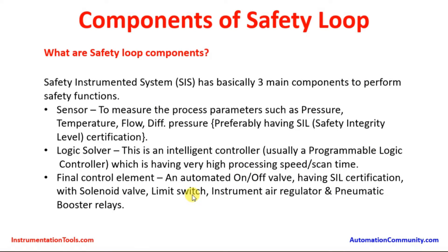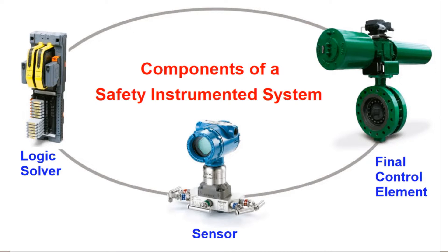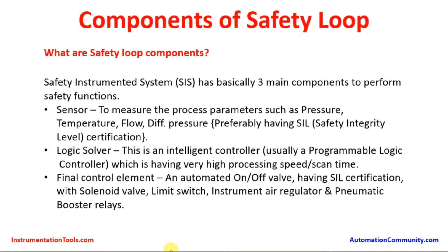The third component is the Final Control Element. This is an automated on-off valve having SIL certification, with a solenoid valve, limit switch, instrument air filter regulator, and pneumatic booster relays as sub-components. When the valve is built with all such accessories, it has to get certified by relevant certifying agencies like Exida, TUV, and other international agencies for qualification of the safety integrity level according to the process requirement.